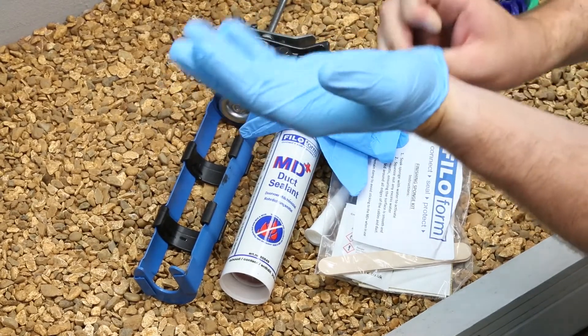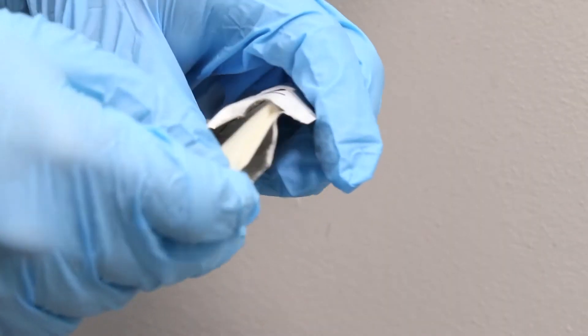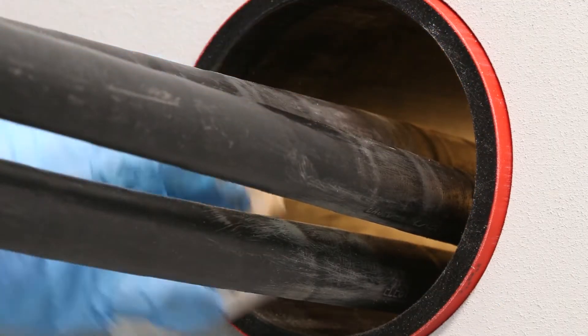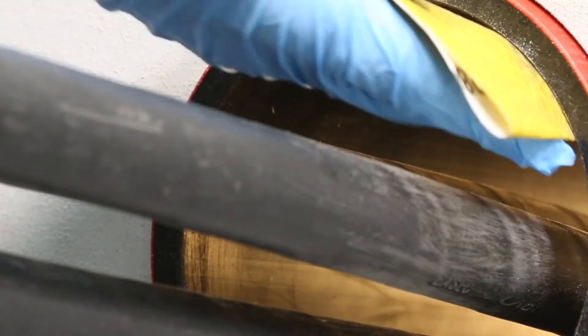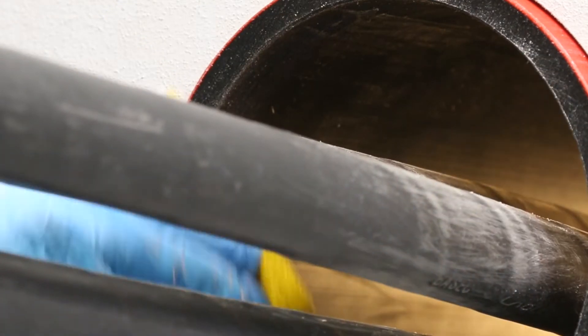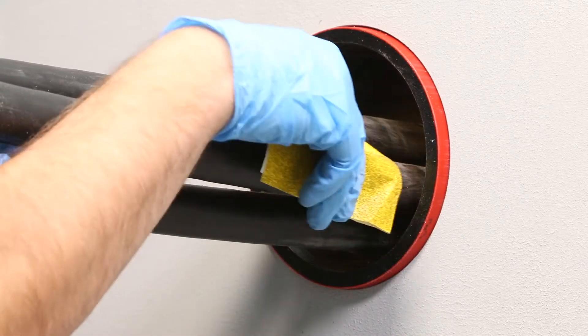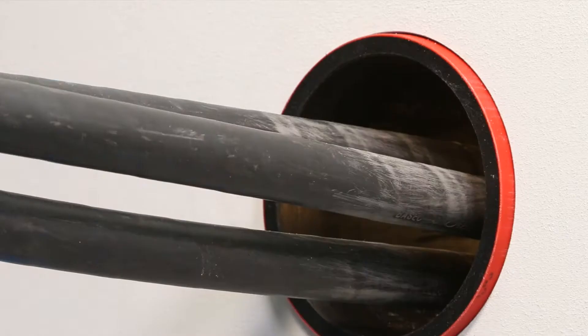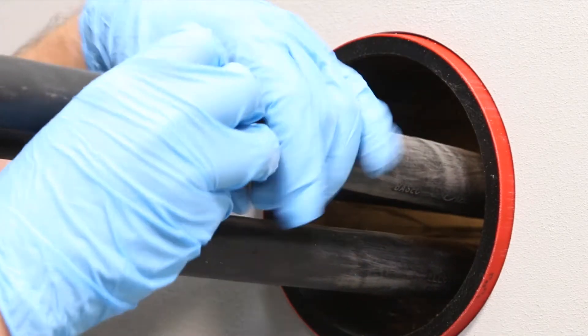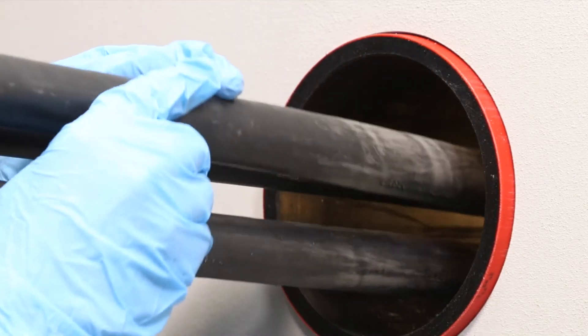The duct and cables or pipes to be sealed must be both clean and dry. Clean and abrade the first 25mm of the cable and 20mm of the inside duct surface. Separate the cables or pipes by at least 5mm from each other and the duct edge.